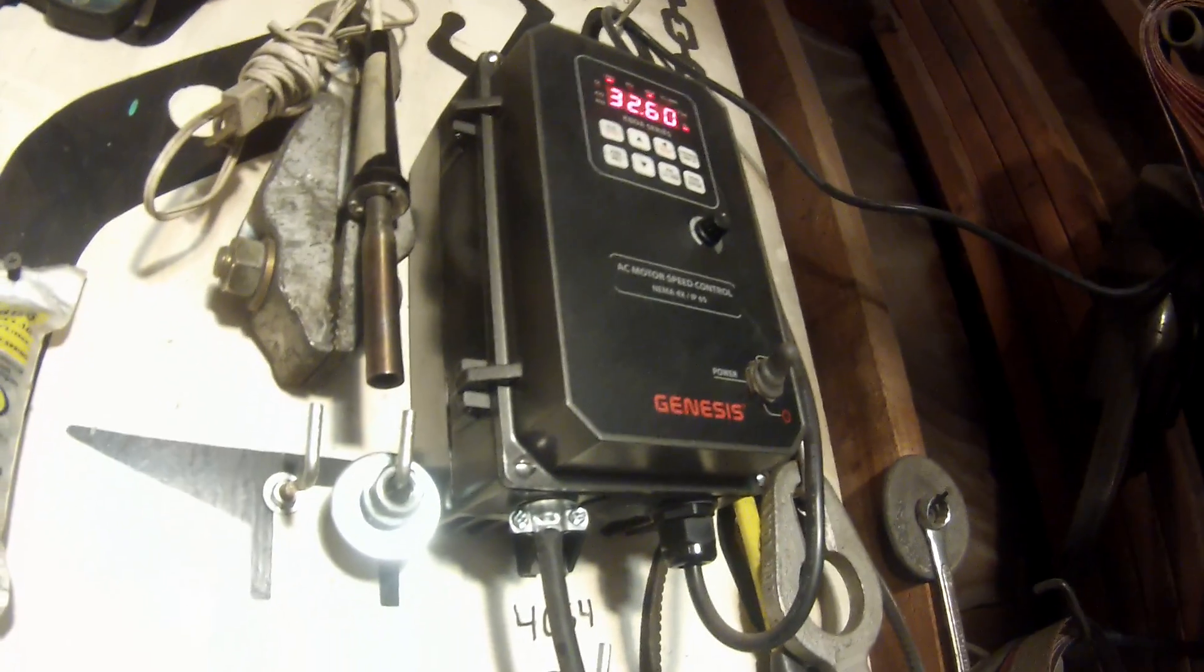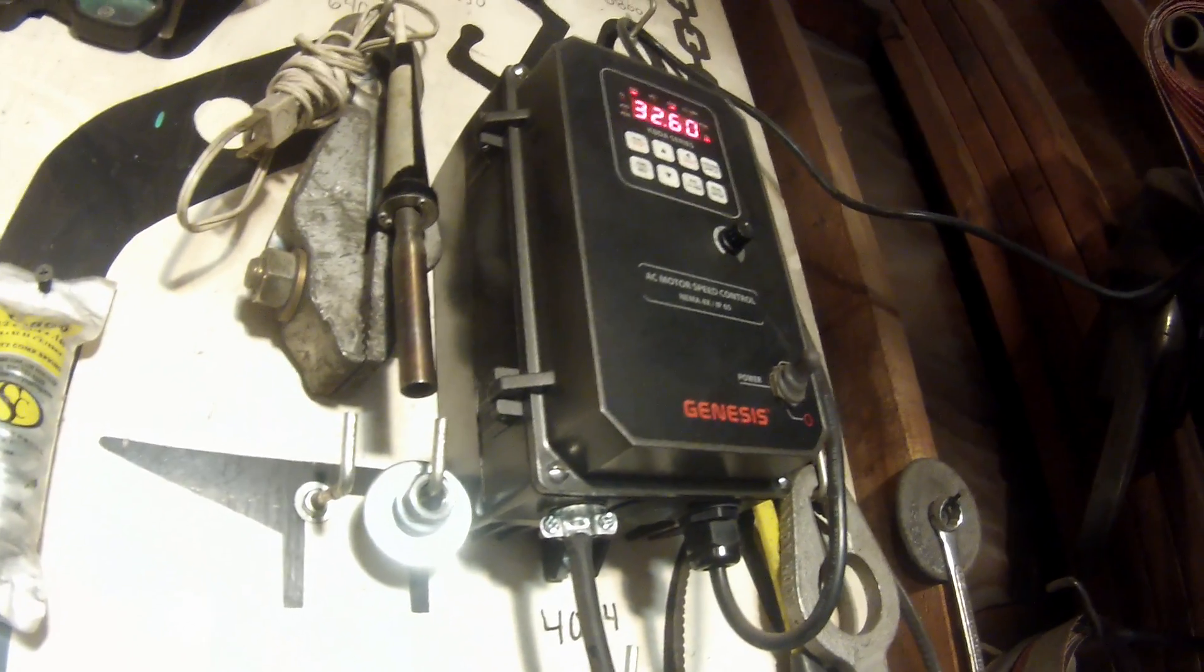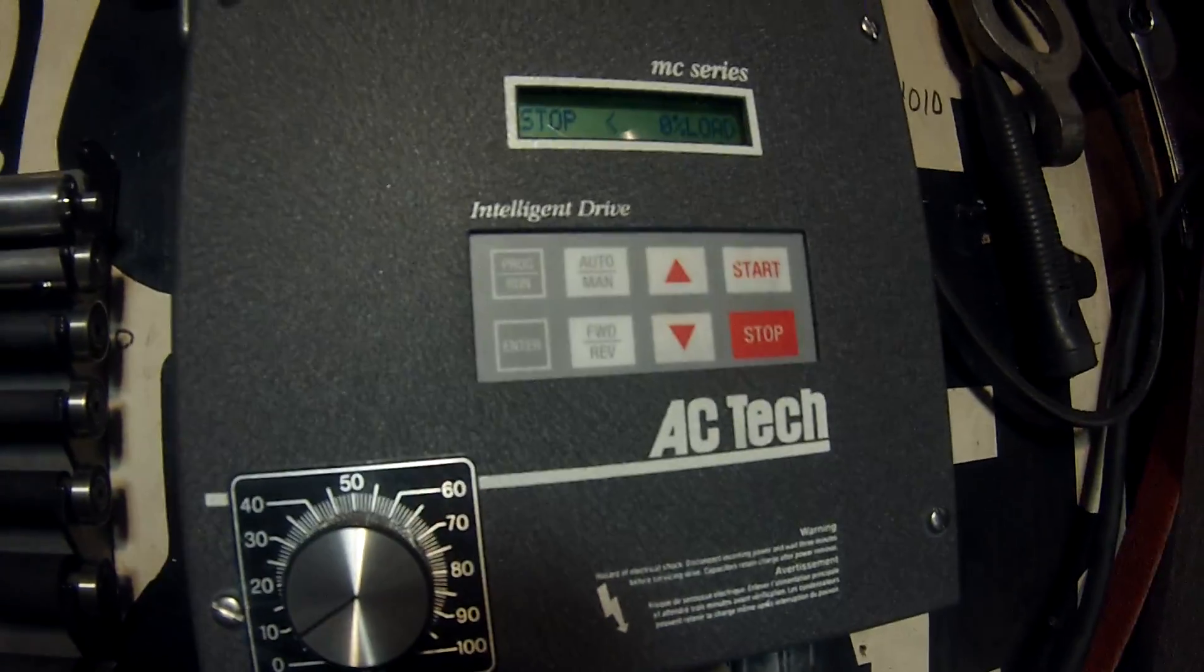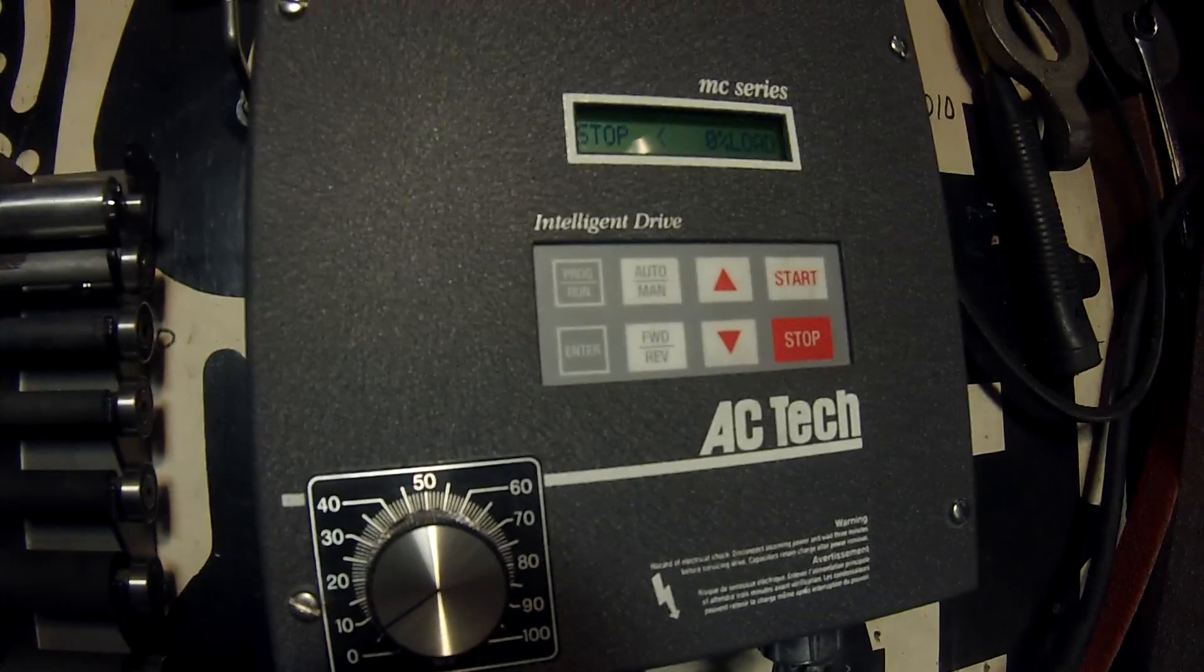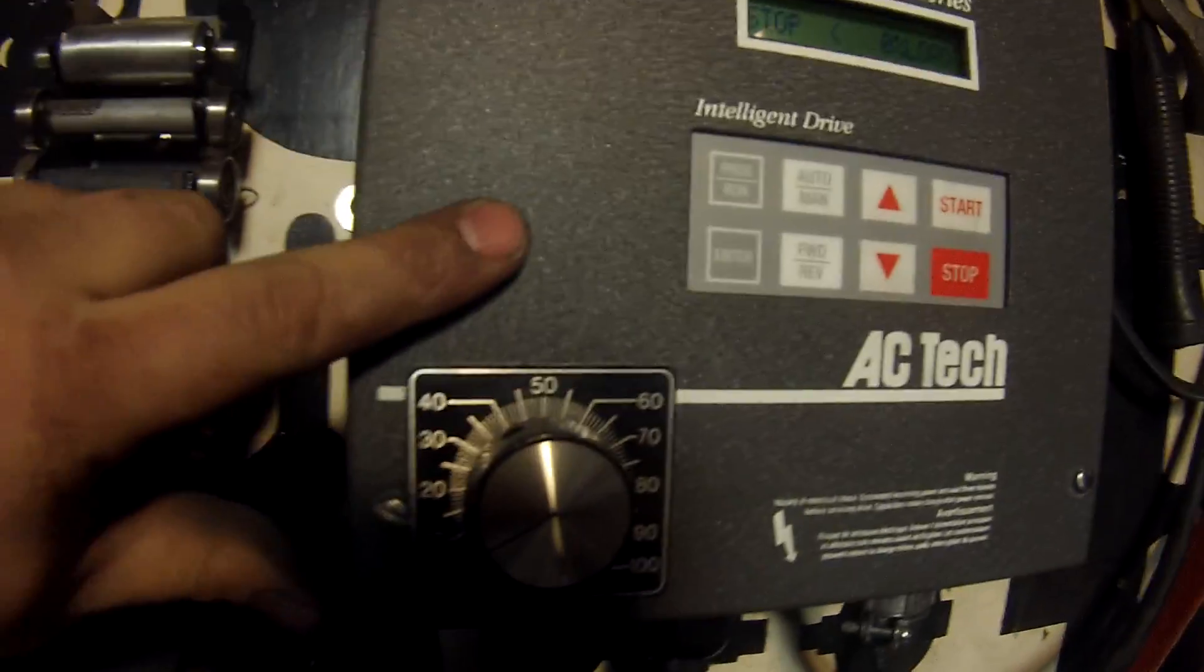I used a regular KB 27, but that one also tripped. So the third drive I chose was this AC Tech Lenze, 2 horsepower 220 volt MC1000 series. This one is really nice.